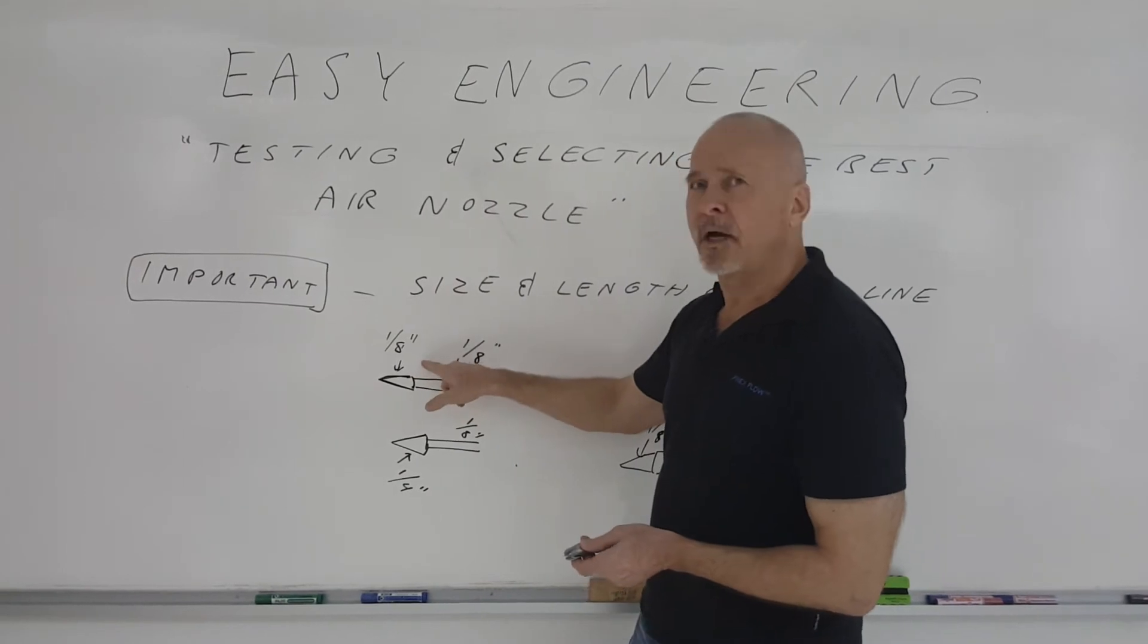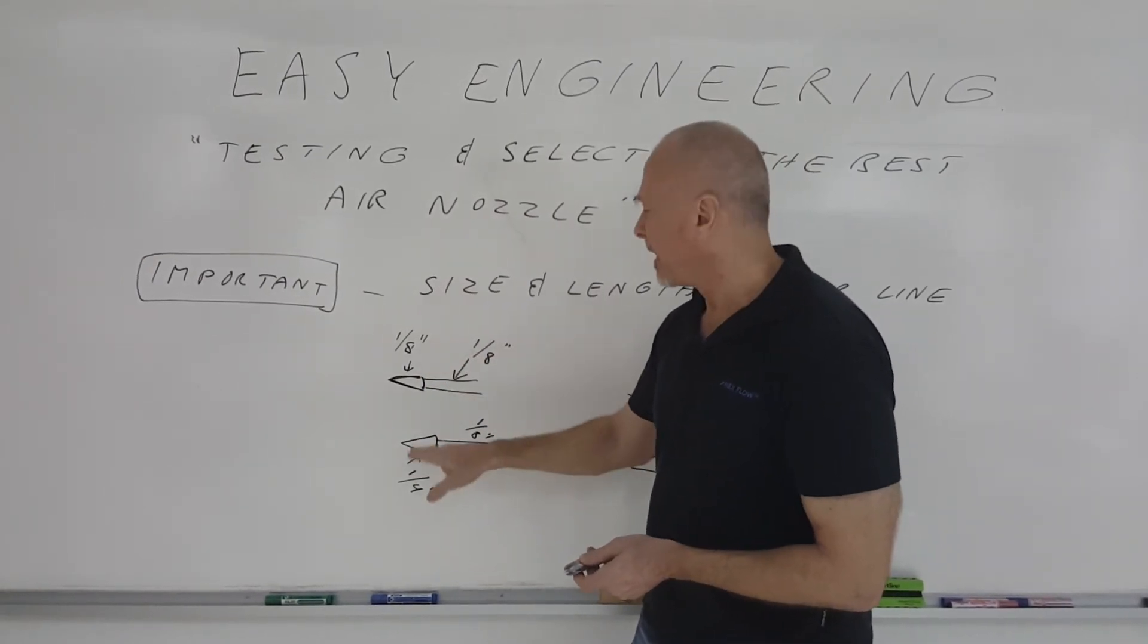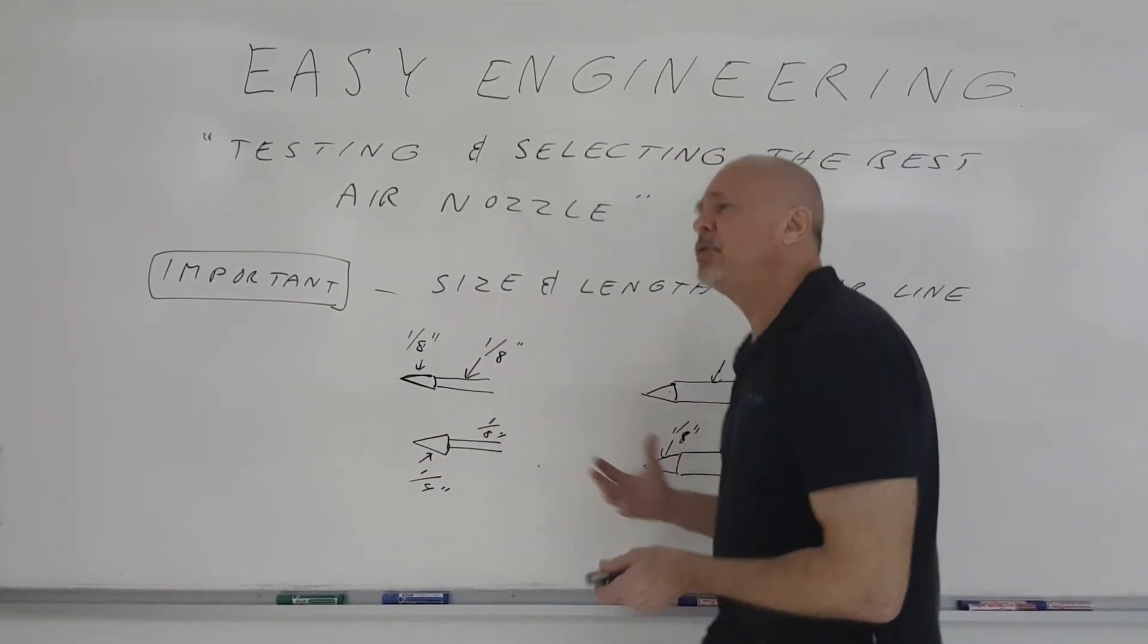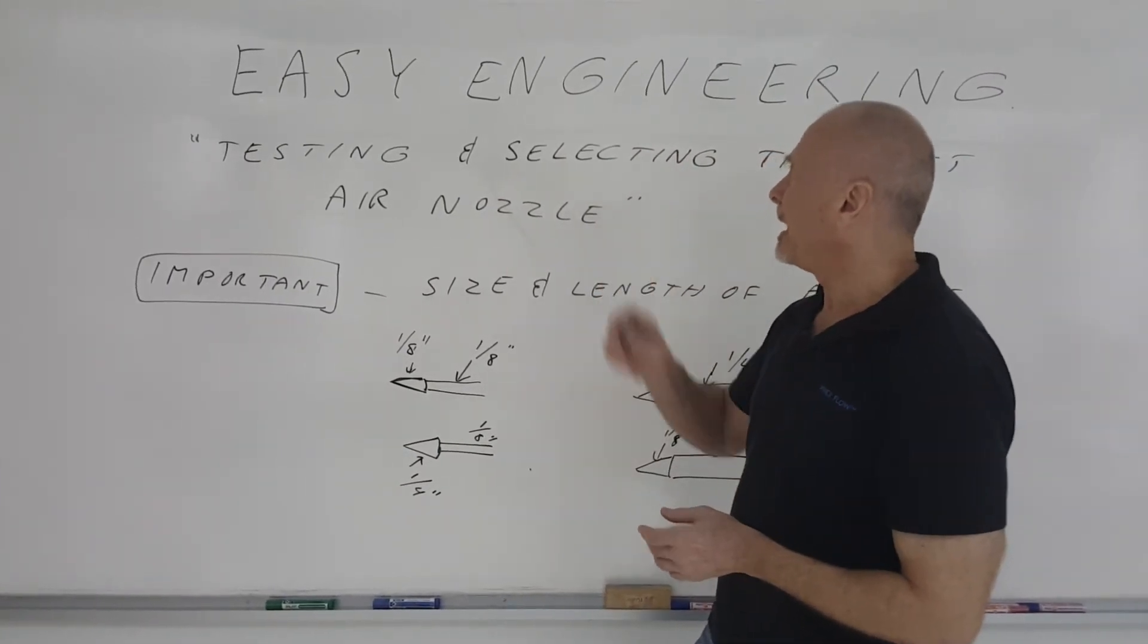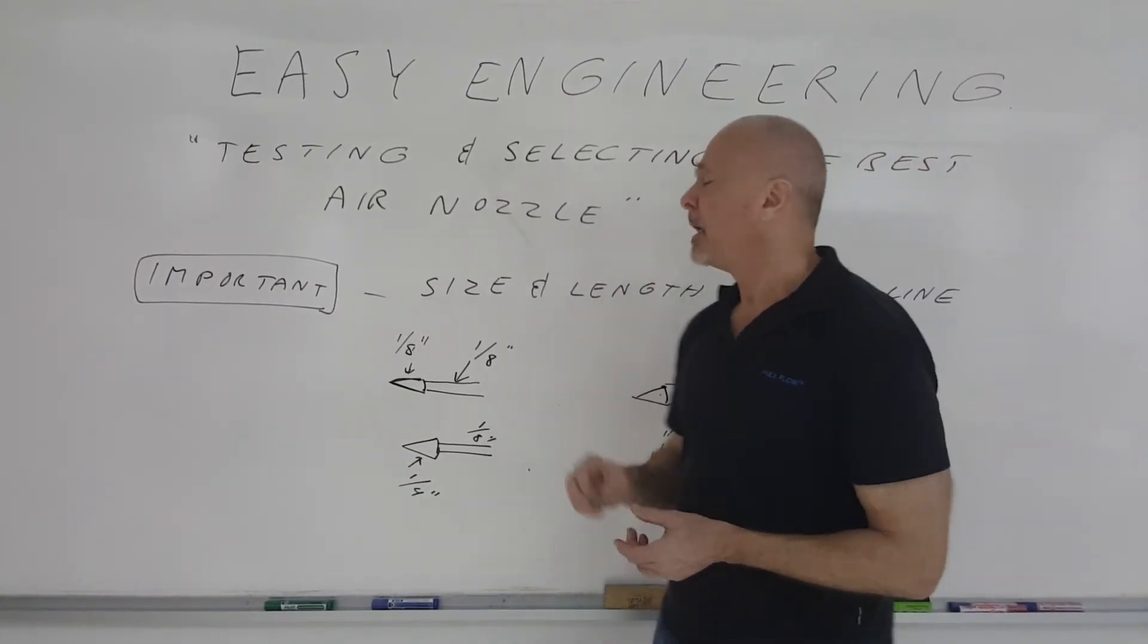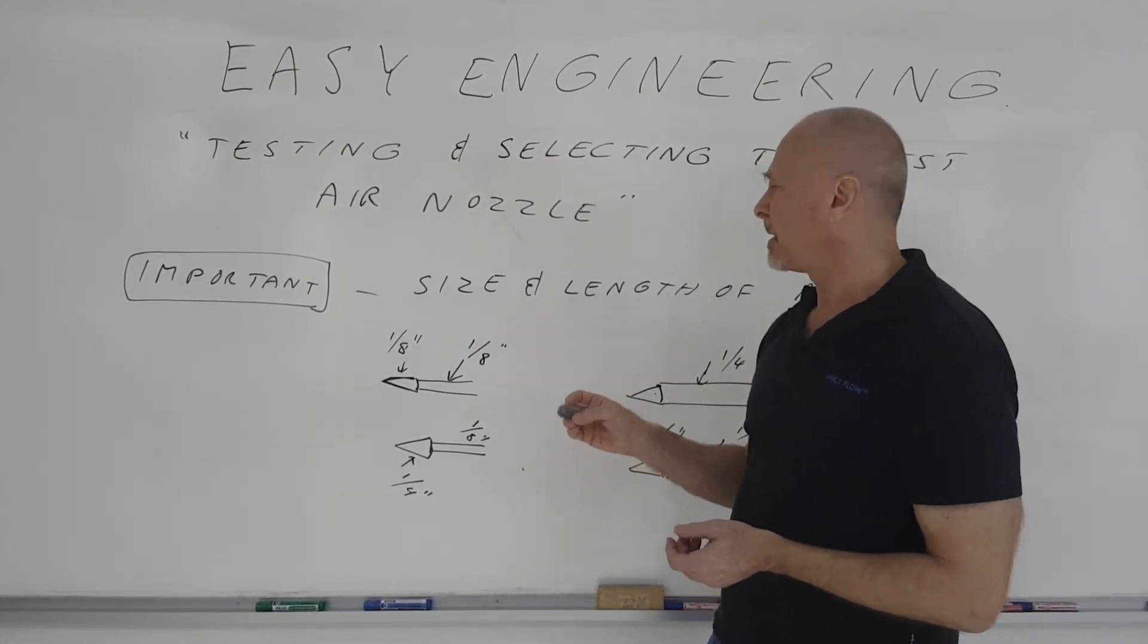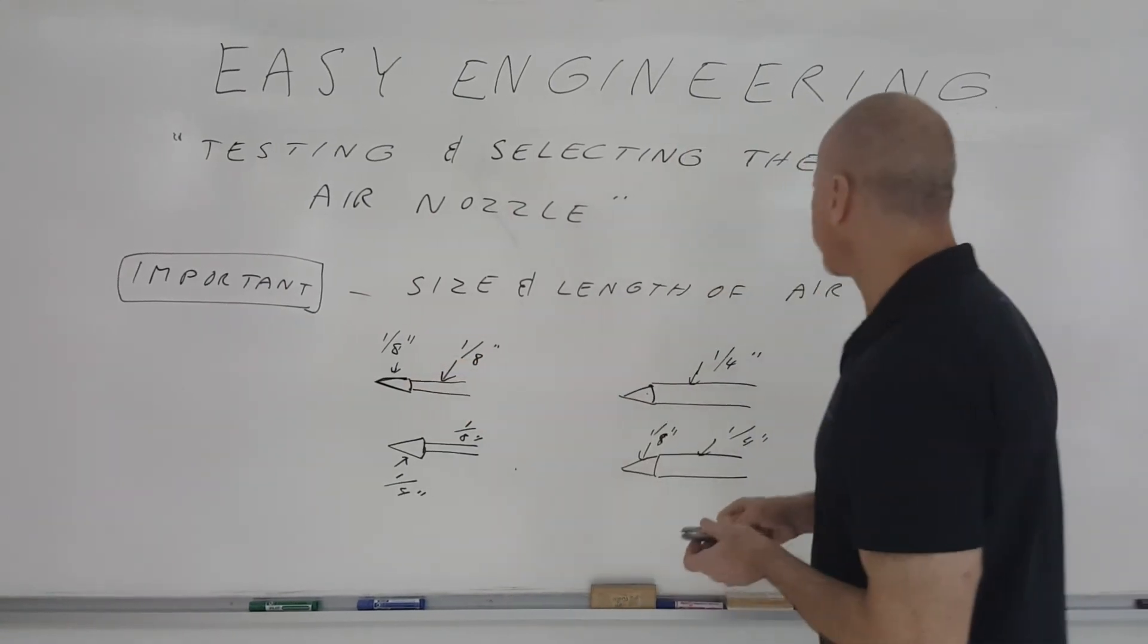So that one-eighth inch nozzle can actually be giving you a higher force than that quarter-inch nozzle, just because the quarter-inch nozzle is trying to draw more flow through it. So typically, the easiest engineering solution is to choose a nozzle for your application that's going to be the same size as the line feeding that particular nozzle.